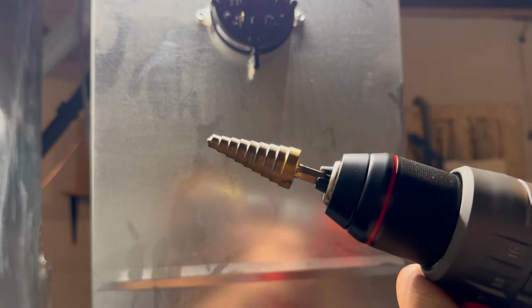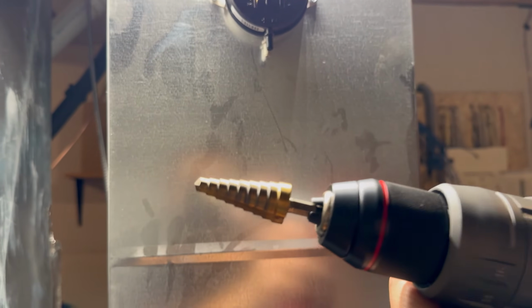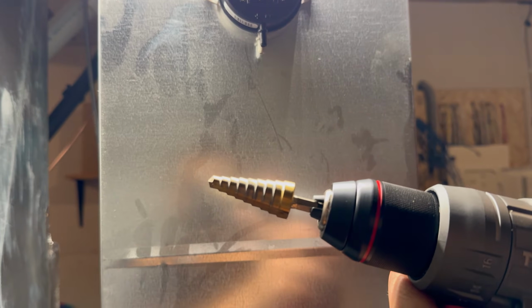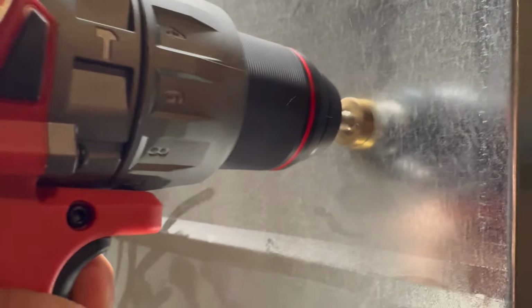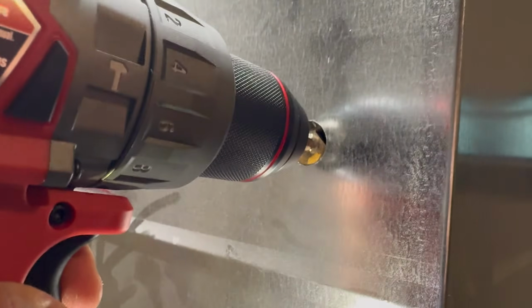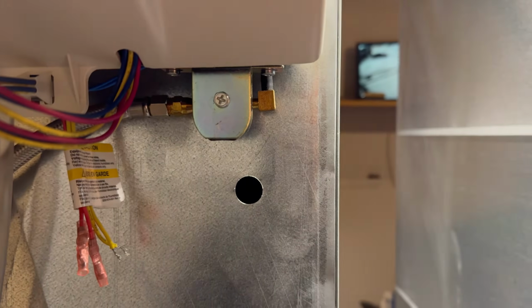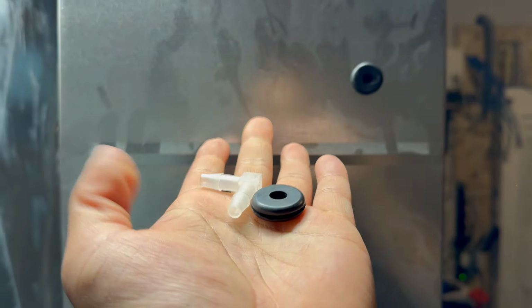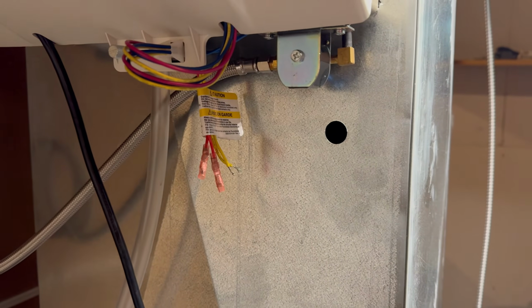First thing we're going to do is drill a 3/4 inch hole on the return side of the ductwork as well as the supply side. The easiest way to do that is with a step drill that'll allow you to cut 3/4 inches. Got your holes drilled on both return and supply side. Add in your rubber grommets that are included in the package, and then you're going to take the plastic elbows and pop them into place, just like so. Repeat on the supply side.